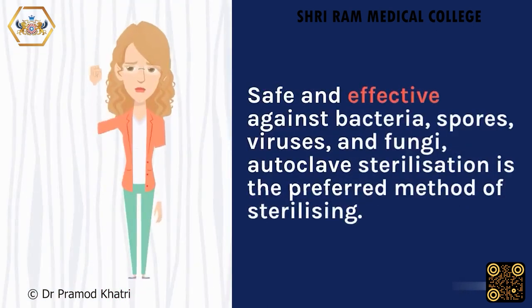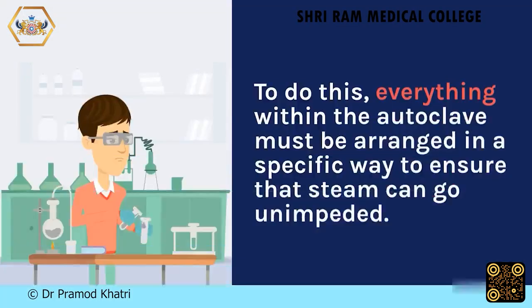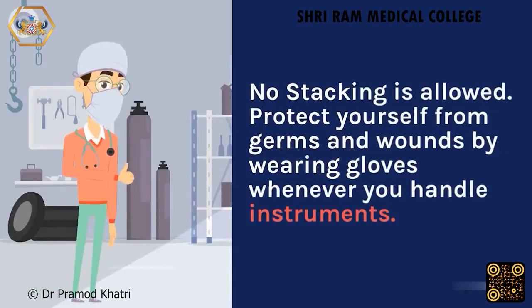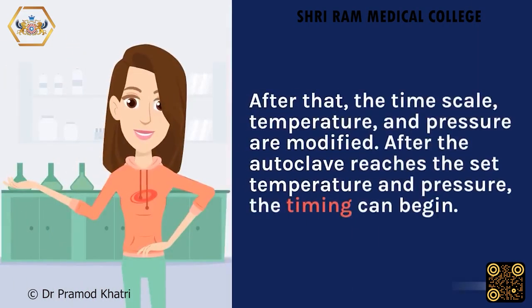Safe and effective against bacteria, spores, viruses, and fungi, autoclave sterilization is the preferred method of sterilizing. To do this, everything within the autoclave must be arranged in a specific way to ensure that steam can go unimpeded. No stacking is allowed. Protect yourself from germs and wounds by wearing gloves whenever you handle instruments. After that, the time scale, temperature, and pressure are modified. After the autoclave reaches the set temperature and pressure, the timing can begin.